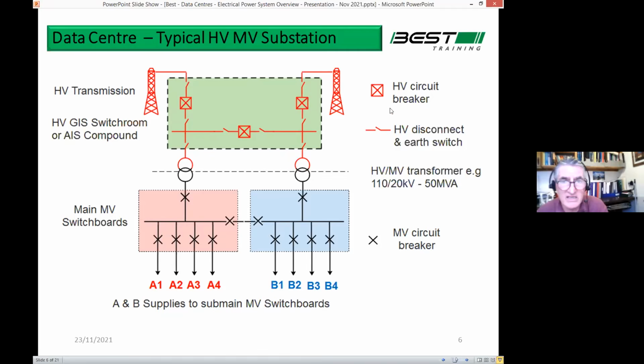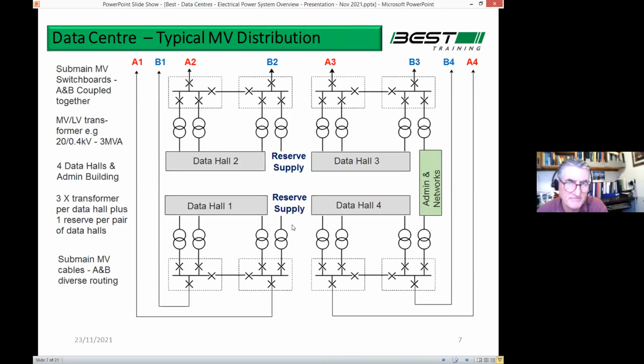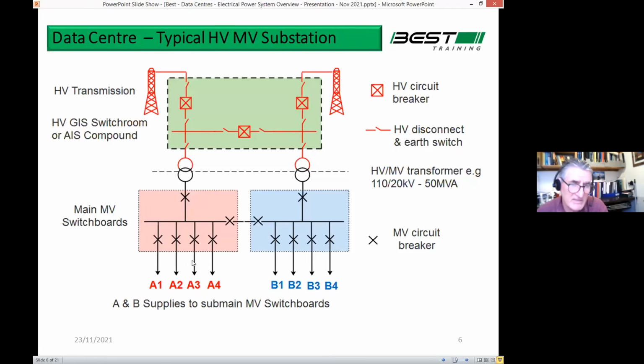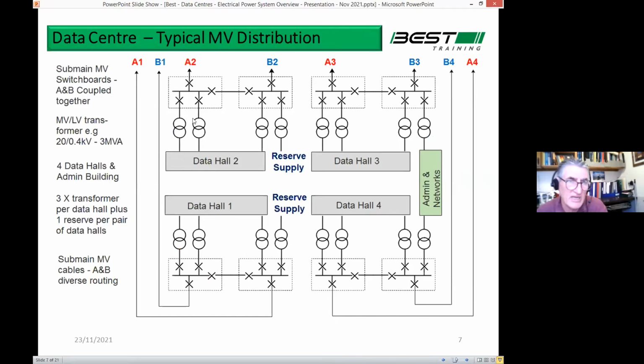So that's the basic high-level overview of the power system, and we're going to look at these various components, keep drilling down all the way to the back of the rack. In this diagram, as an example, there are 4 supplies on the A side and 4 supplies on the B side. In the next diagram, you're going to pick those up and see what happens with them. You can see there's A1, B1, A2, B2, etc. There are multiple ways of configuring the power system, but this will be fairly typical.